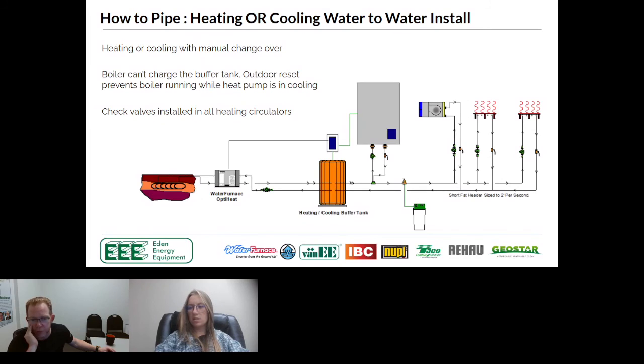So the idea of this boiler placement here is we let the heat pump heat this buffer tank as hot as we can get it. If it's a water to water, typically they top out at 120 degrees. If it's an air to water, they all top out around 140 degrees. So I'm going to charge this buffer tank in the case of the air to water to 140 degrees. And this boiler is only lifting it from 140 to 180. So it actually is quite efficient because we're lifting it 40 degrees instead of lifting it whatever the distance may be. So hopefully that makes sense.